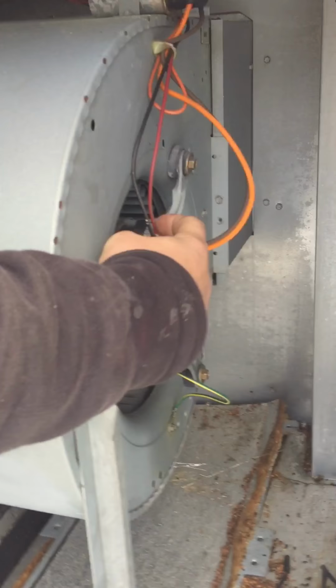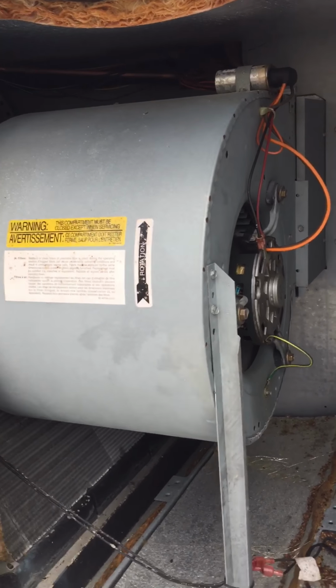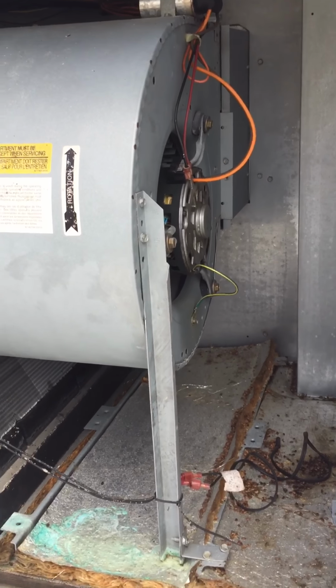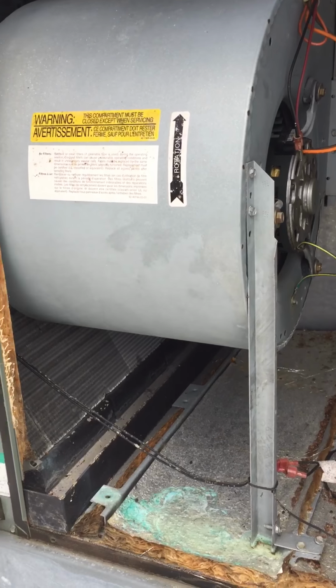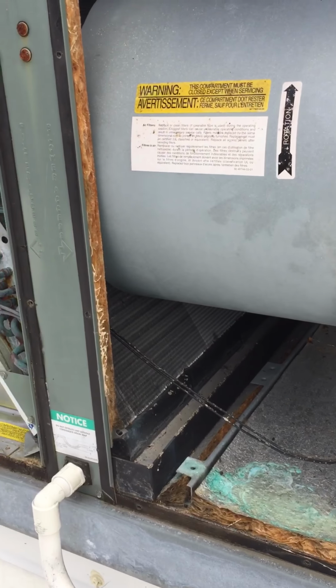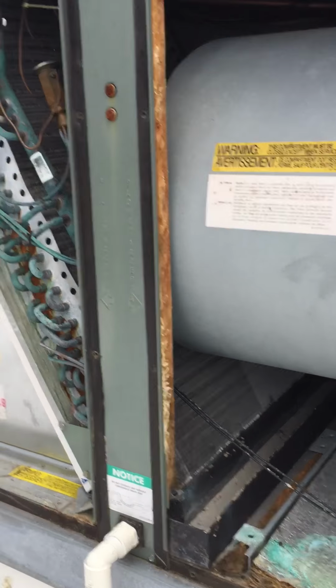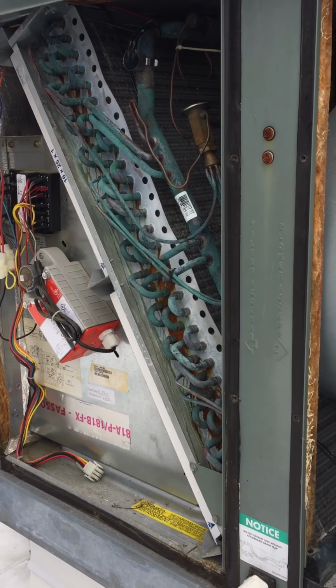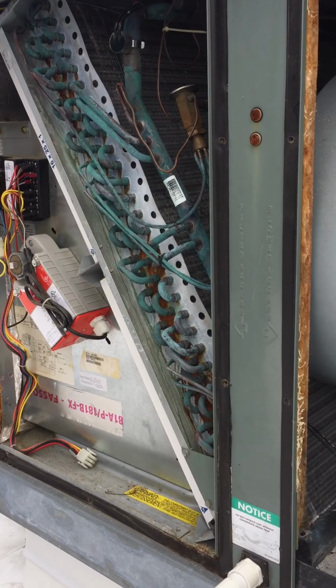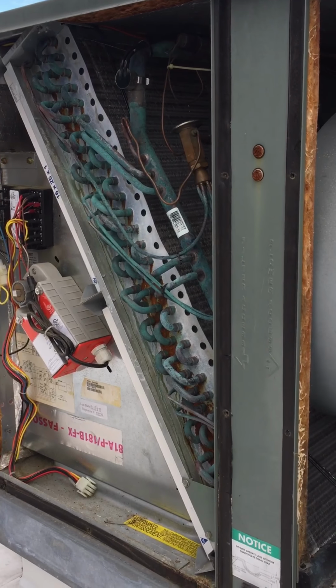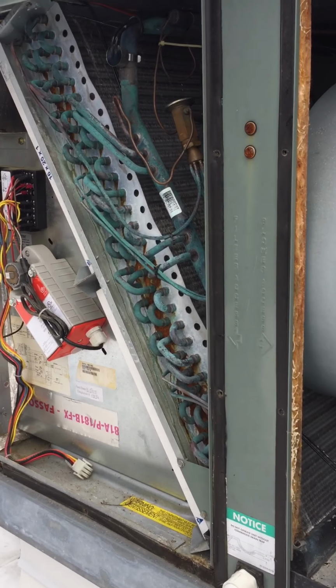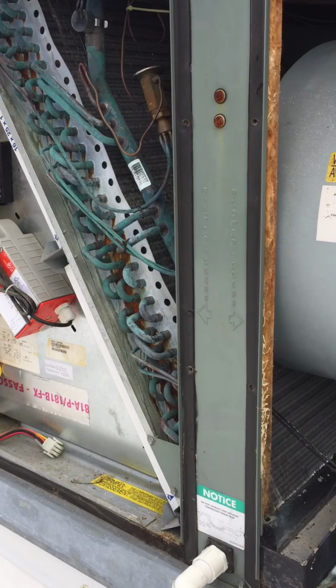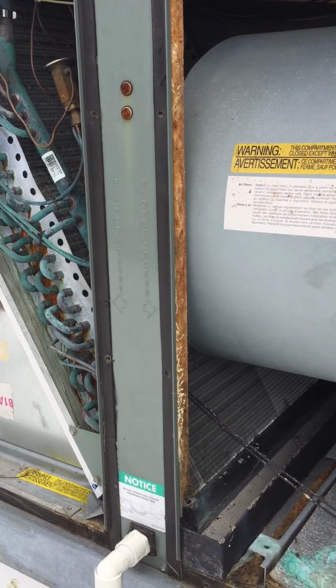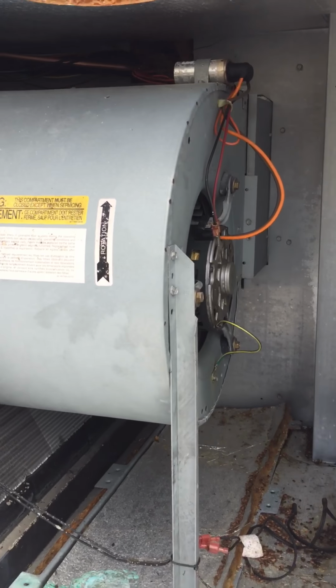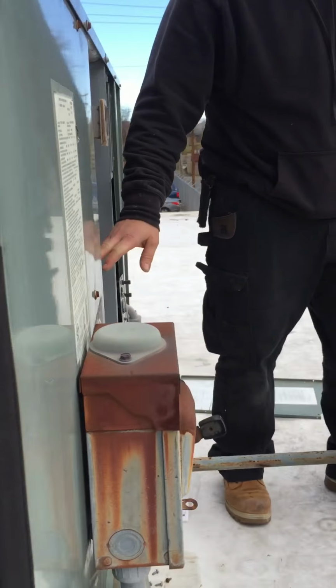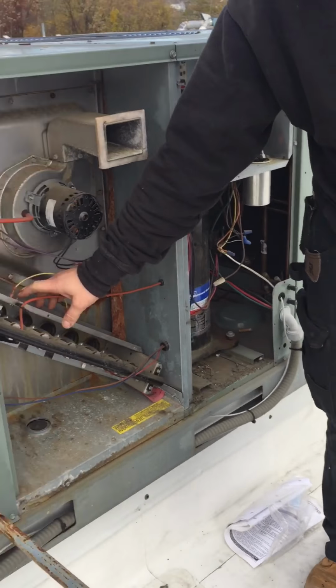I haven't turned it on yet, but we'll see what else is going on with it. The combination of the filters is what would cause that, along with low fan speed and undersized ductwork. So the ductwork is undersized too? It's pretty difficult to know, because we'd have to get a crane, lift this thing up, and do the investigation, which would be crazy money to do. But if we fix everything else, it should help a lot. And since the exchanger is not burned out, we can assume the ductwork probably isn't too small, because it isn't burned out yet.